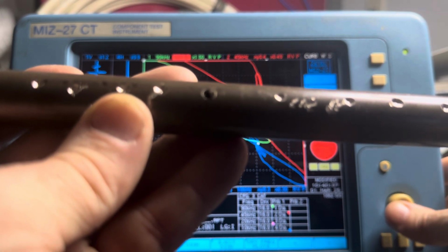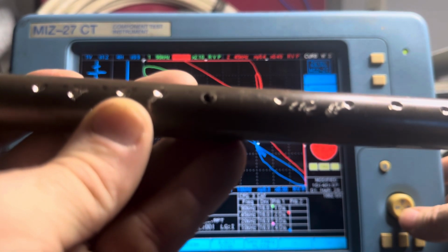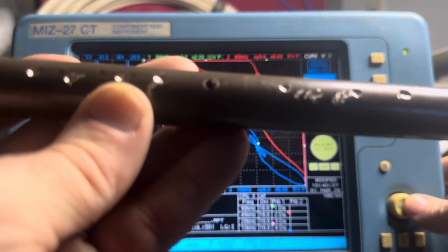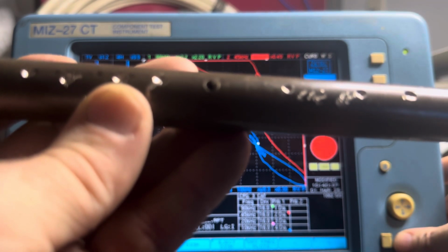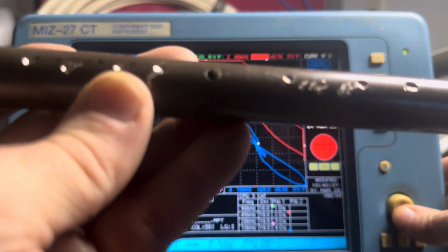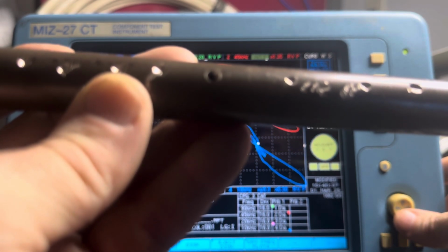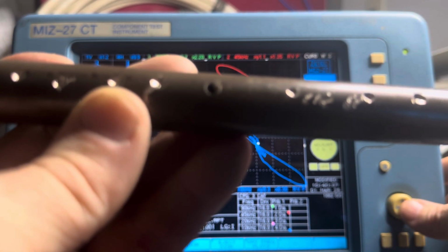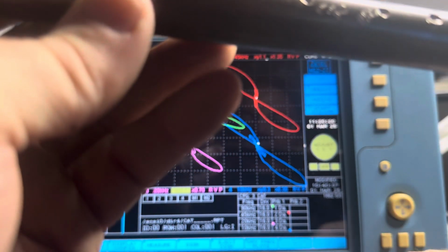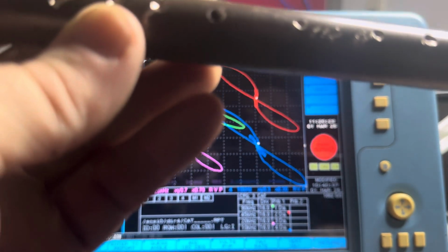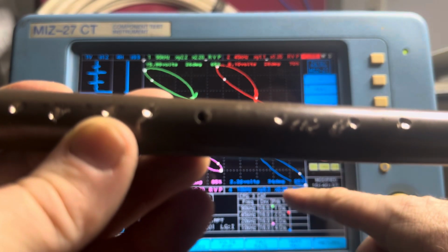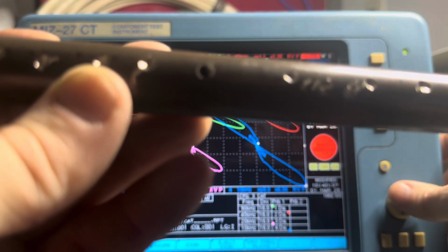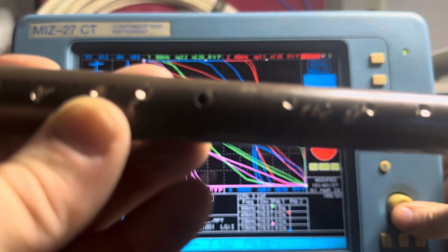So obviously the bigger the hole, the larger the signal, because the signal amplitude is based on the length, width, and depth of the total volume of metal missing. So we know when the hole, which is through-wall, got larger because our drill bit has a larger diameter, the signal got bigger. And the reason the phase is dropping is because more surface eddy currents are disturbed than before. All right, so let's go there and hit max rate. 26, 29, 34, and 34. They dropped even a little bit more. So now we're getting up to the last two sets.